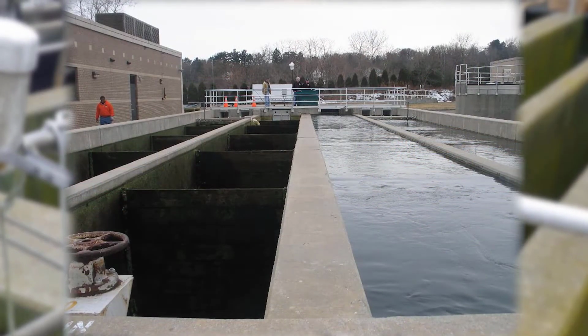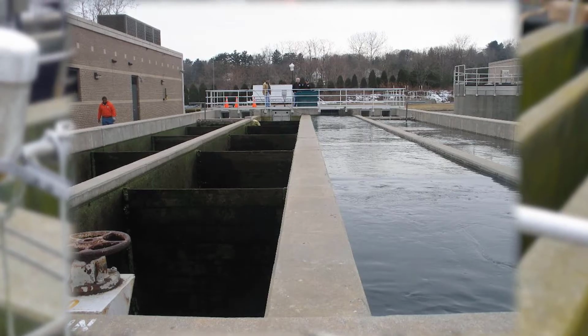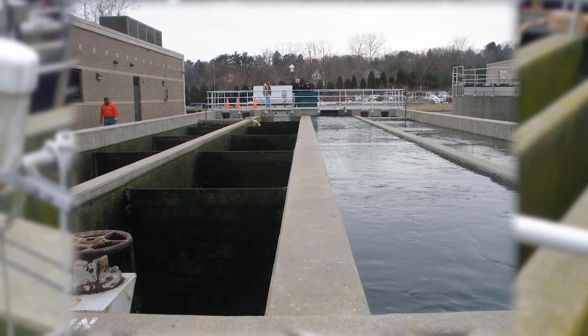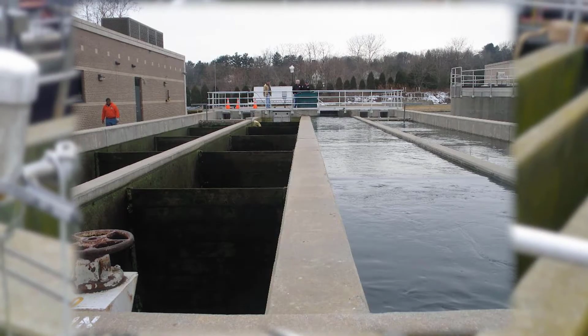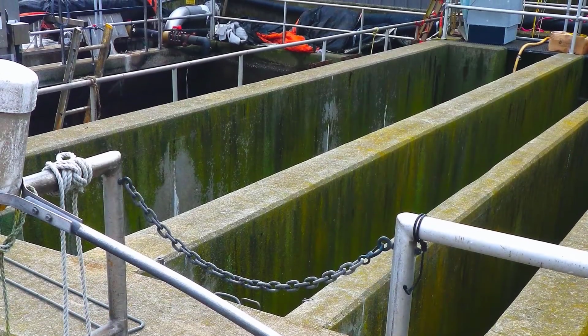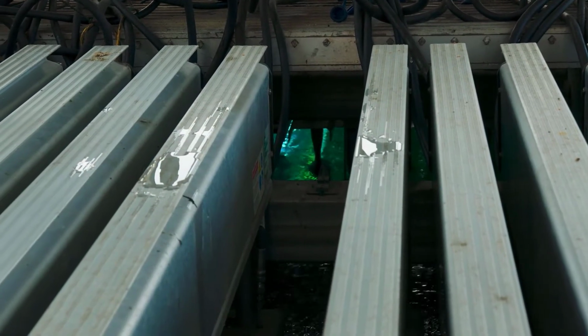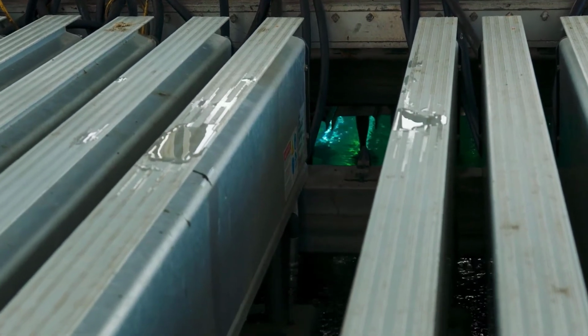It also has a residual effect which prolongs disinfection after the initial treatment. Unfortunately, it can be toxic to aquatic life, so many states require dechlorination. Studies conducted by FDA and others have shown that chlorine disinfection may not be as effective against viruses and parasites compared to UV. Ultraviolet disinfection uses UV radiation to penetrate the cell wall of an organism and destroy the cell's ability to reproduce. It is very effective at deactivating viruses, spores, and cysts in addition to bacteria.